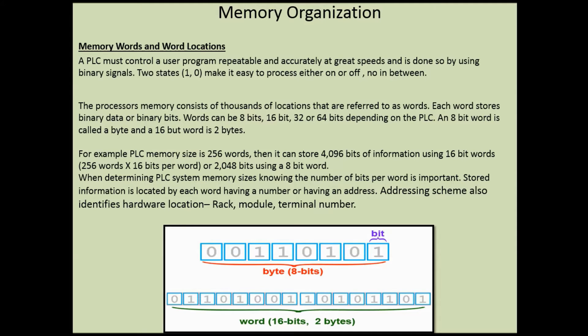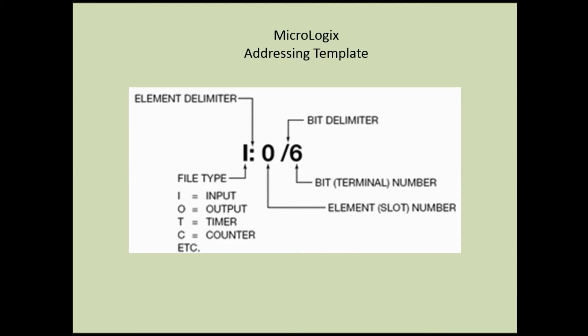When determining a PLC system memory size, knowing the number of bits per word is important. Stored information is identified by each word having a number or address. Addressing schemes also identify hardware location, rack, module, and terminal number. Looking at the MicroLogix addressing template: the first part of the address is always the file type. For an input it's I, for outputs it's O, timers T, counters C. When you have something wired into an input module it will always start with I, and if you use a timer it always starts with T. That is the file type - the location where the information will be stored.